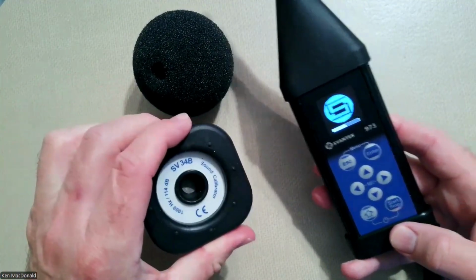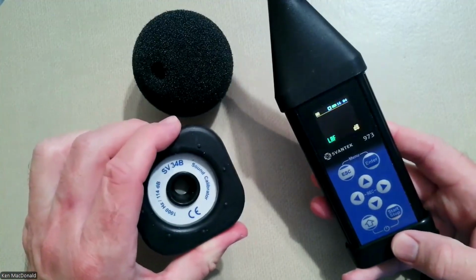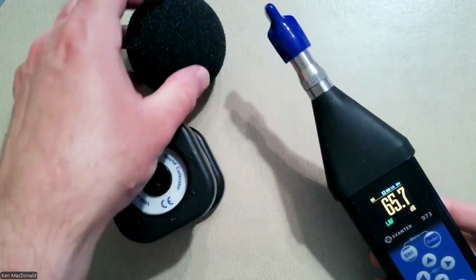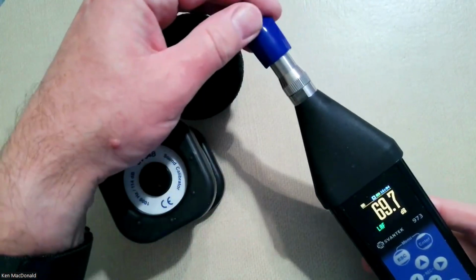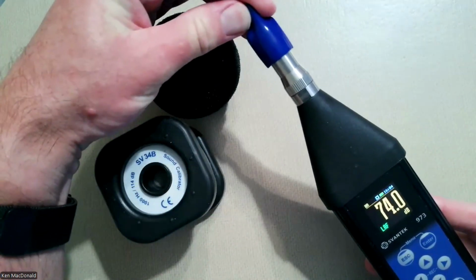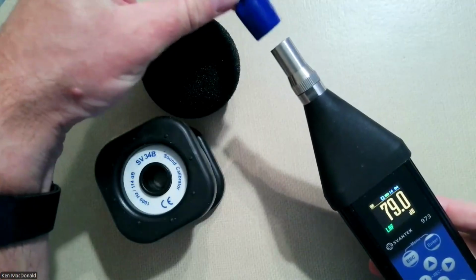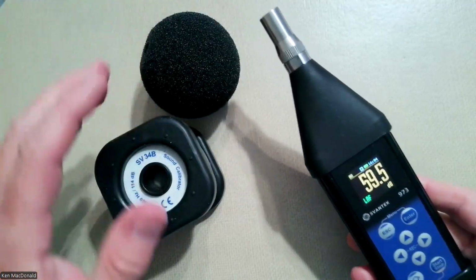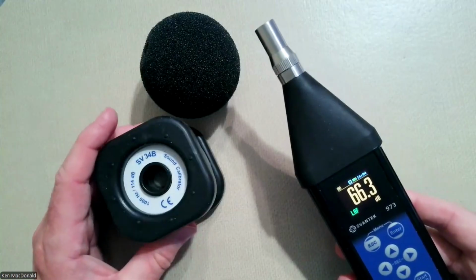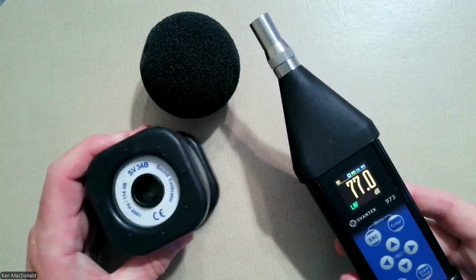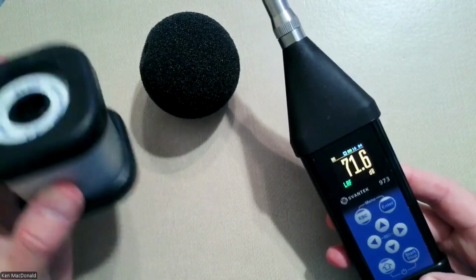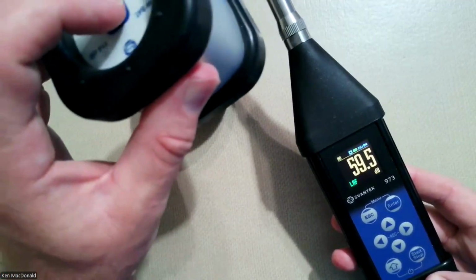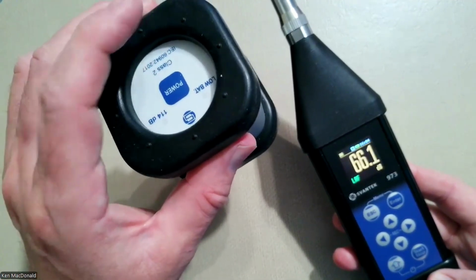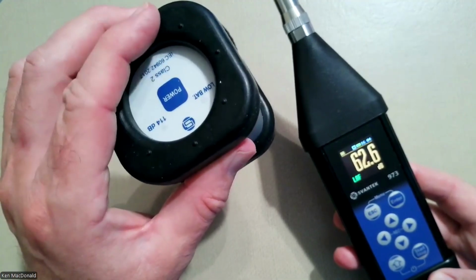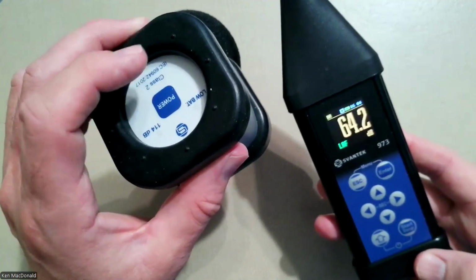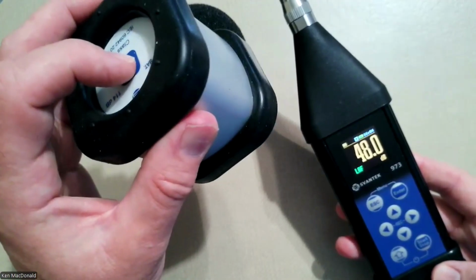This is the Class 2 calibrator, the SV34B. I've removed the windscreen and also this protective cover here. When we remove this cover, we want to pull this straight off and not rotate it at all. And I'll show you more about why we don't want to do that later. But so I have the meter running, and I'm going to click on the calibrator, and there is a video on adding the batteries to this or changing the batteries in this, and also changing the batteries in the meter.